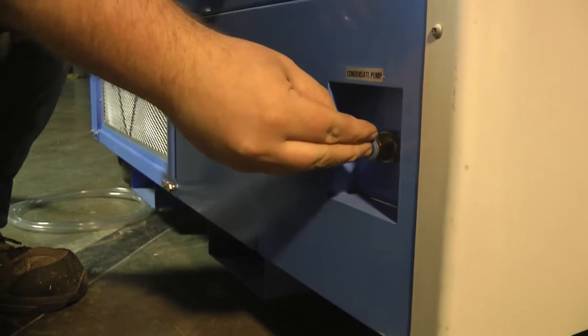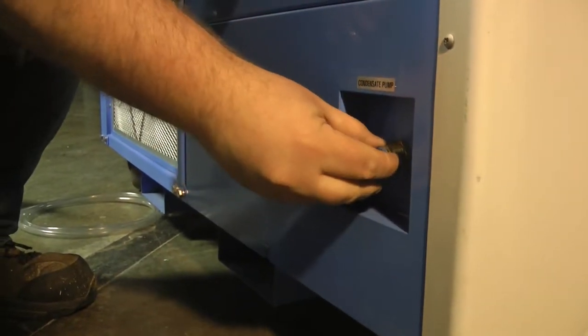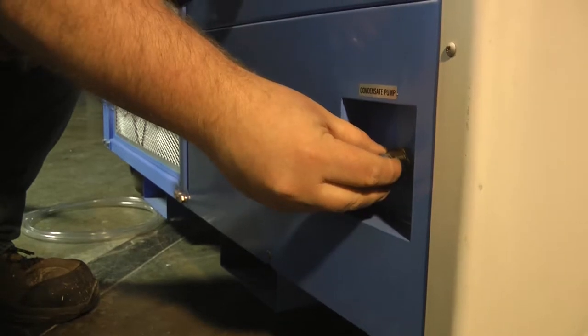The flaw that we've come across over time is this quick connect fitting. As water gets done being pumped, any water that's left in the line rushes back down towards this fitting. There's a check valve on the pump but unfortunately there's not a check valve on this fitting.